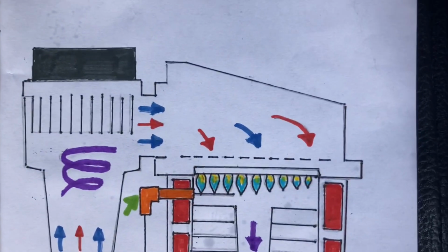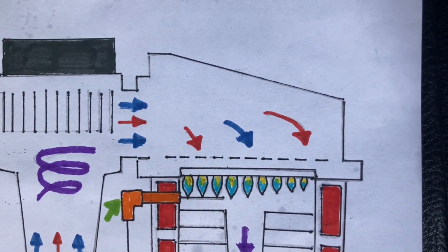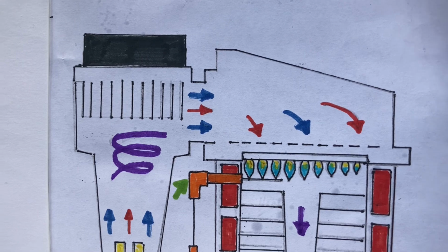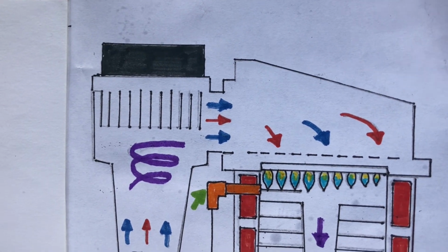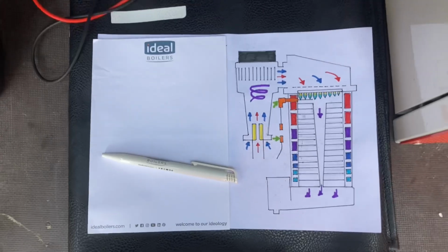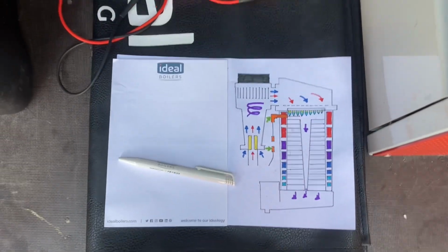Once that burner's blocked, you ain't unblocking it. And like I said, the way to test the burner on a condensing boiler is very, very difficult, but I've figured out a way to do it. And yeah, give it a try if you're stuck.